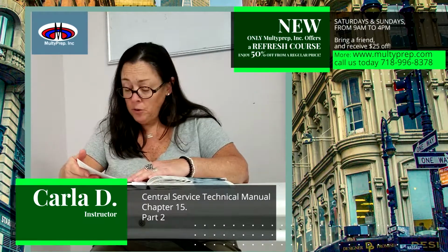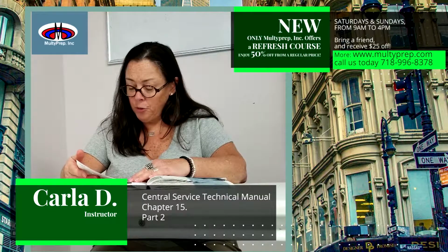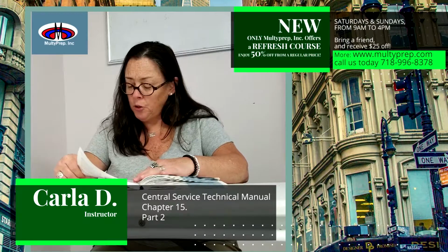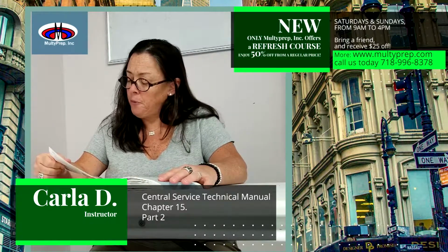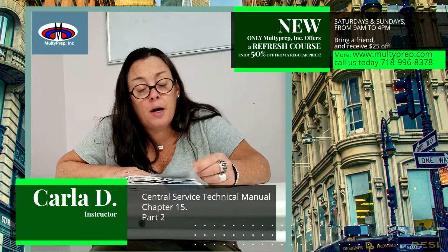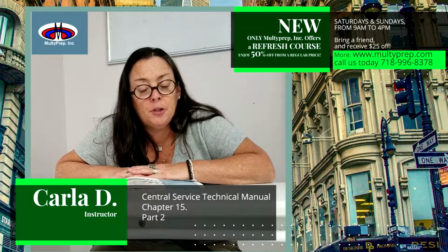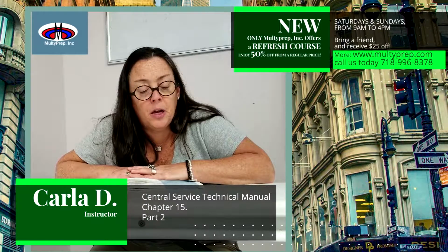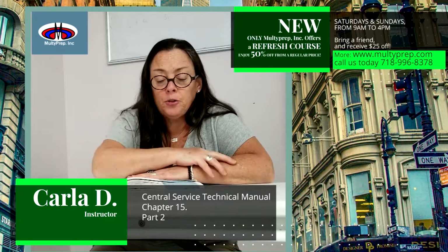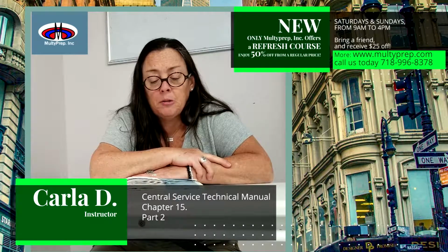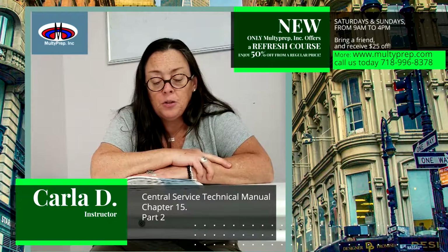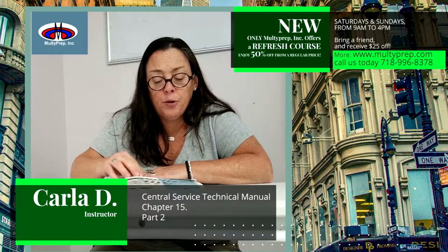Sterilizer performance monitors. Hydrogen peroxide gas plasma sterilizers should be monitored with physical, chemical, and biological indicators. The sterilizer performance monitors include physical monitors. Hydrogen peroxide plasma sterilizers operate on a fixed automatic cycle controlled by a microprocessor. All critical parameters are monitored during the operation of the cycle, and a printed record documenting the process parameters is provided at the end of each cycle. If any process parameter does not meet established acceptable limits, the cycle will be canceled and the printed record will indicate the reason for the cancellation.